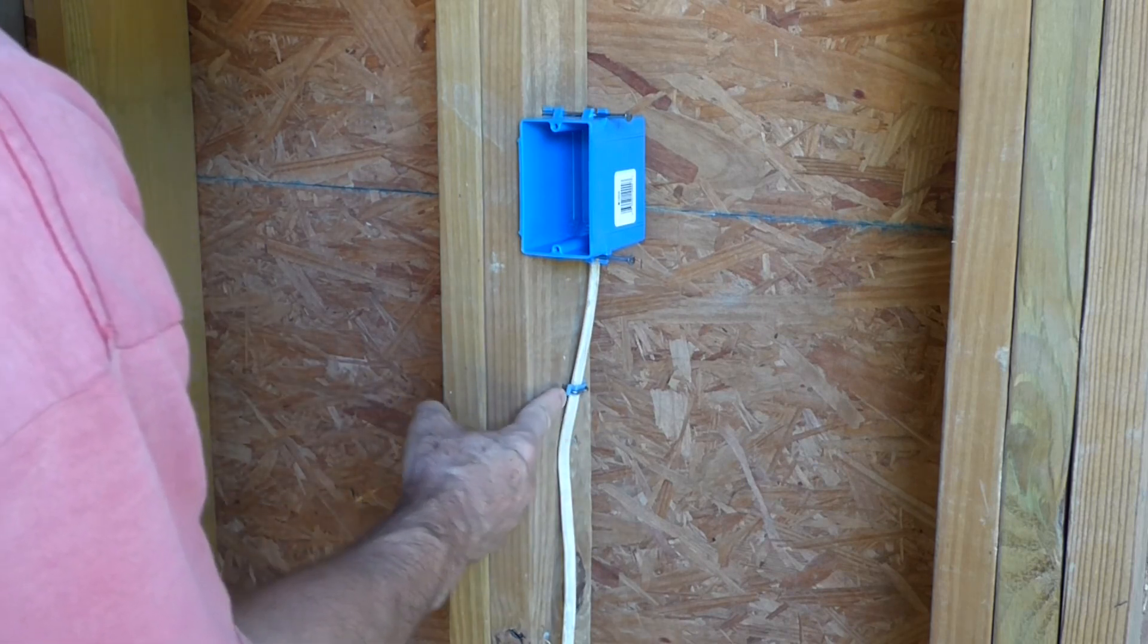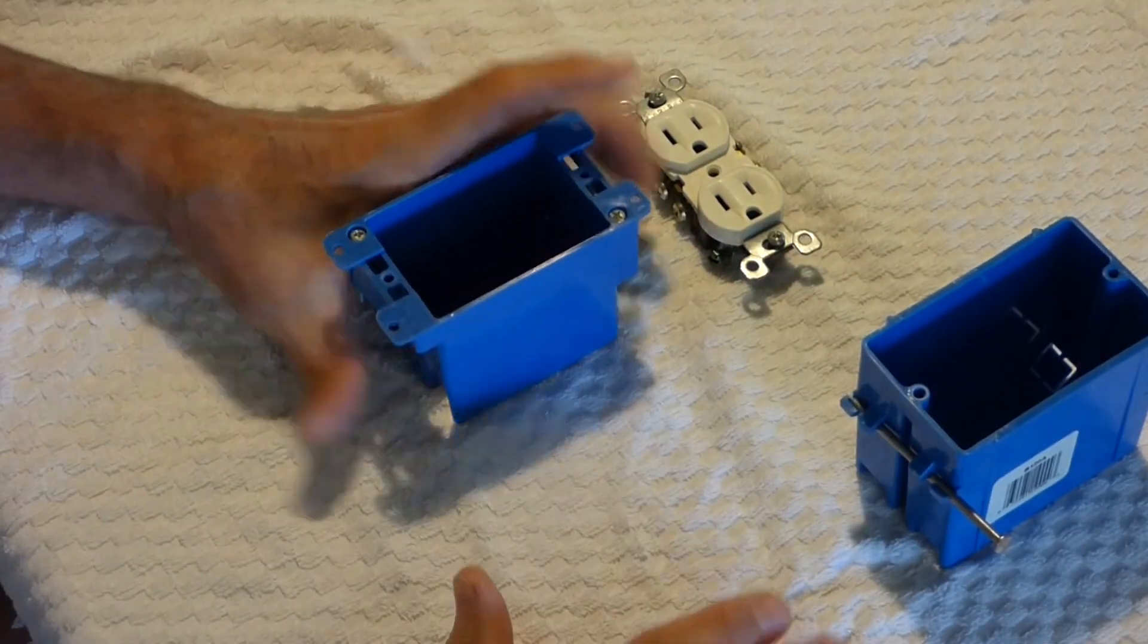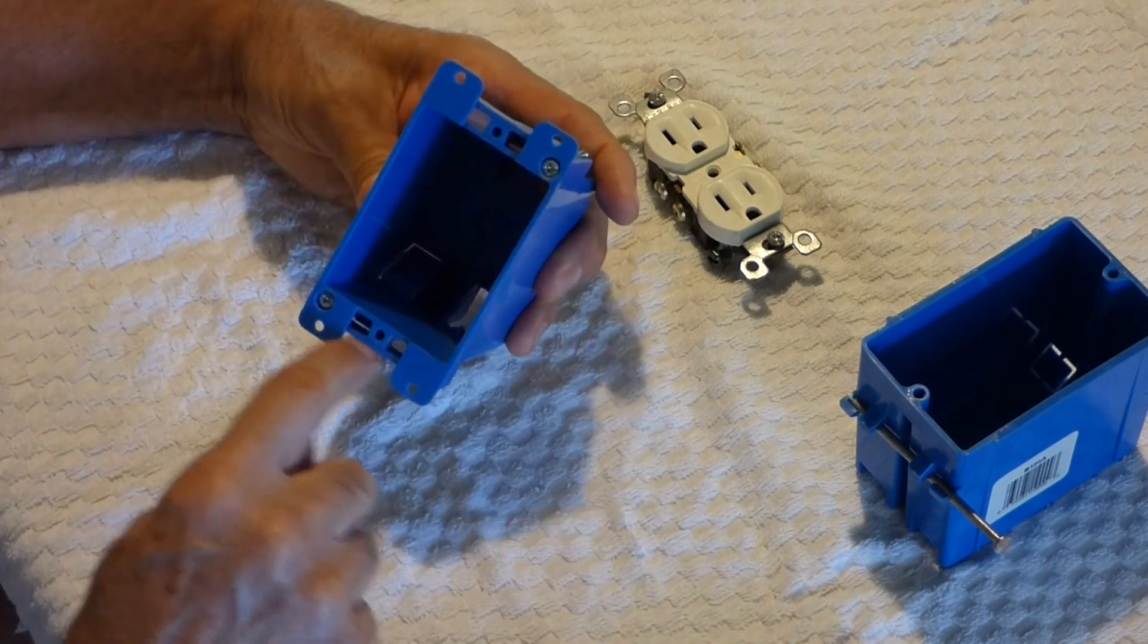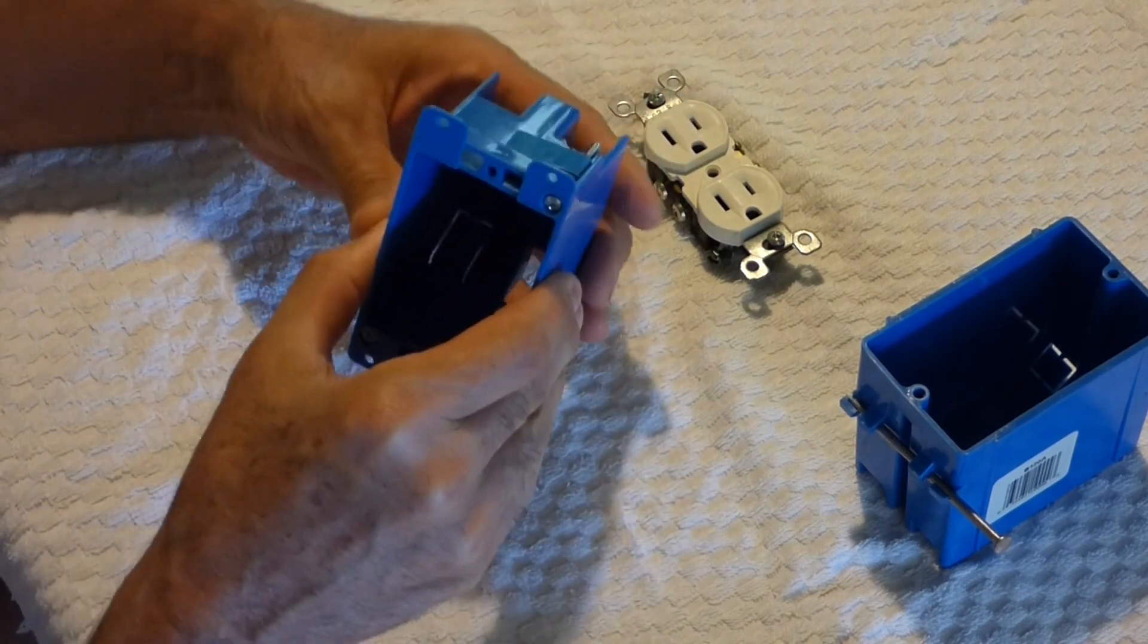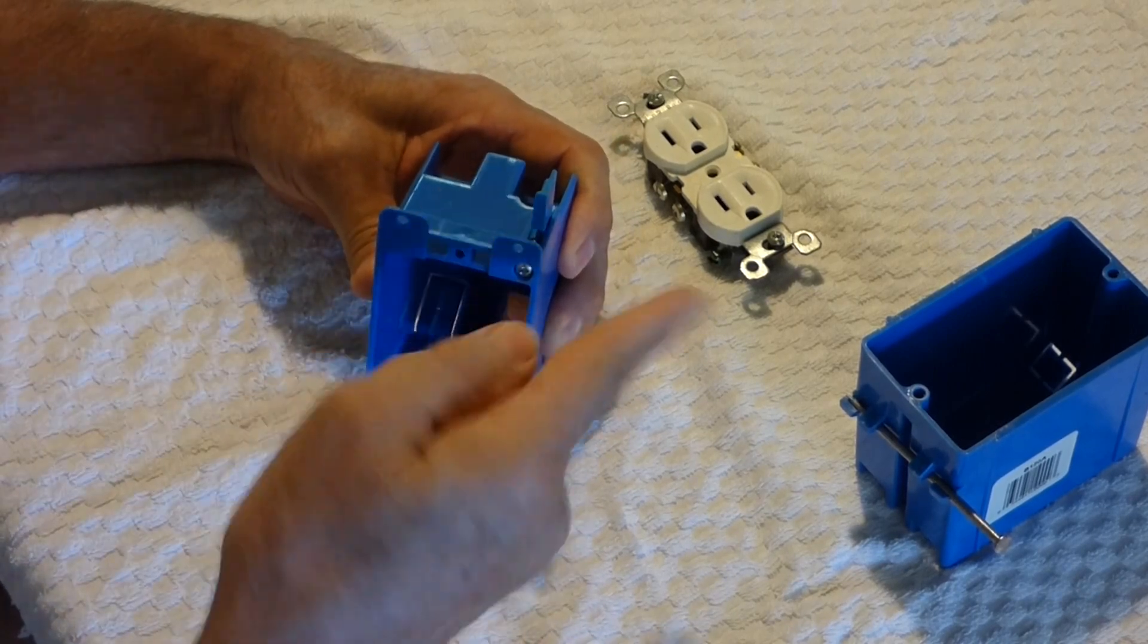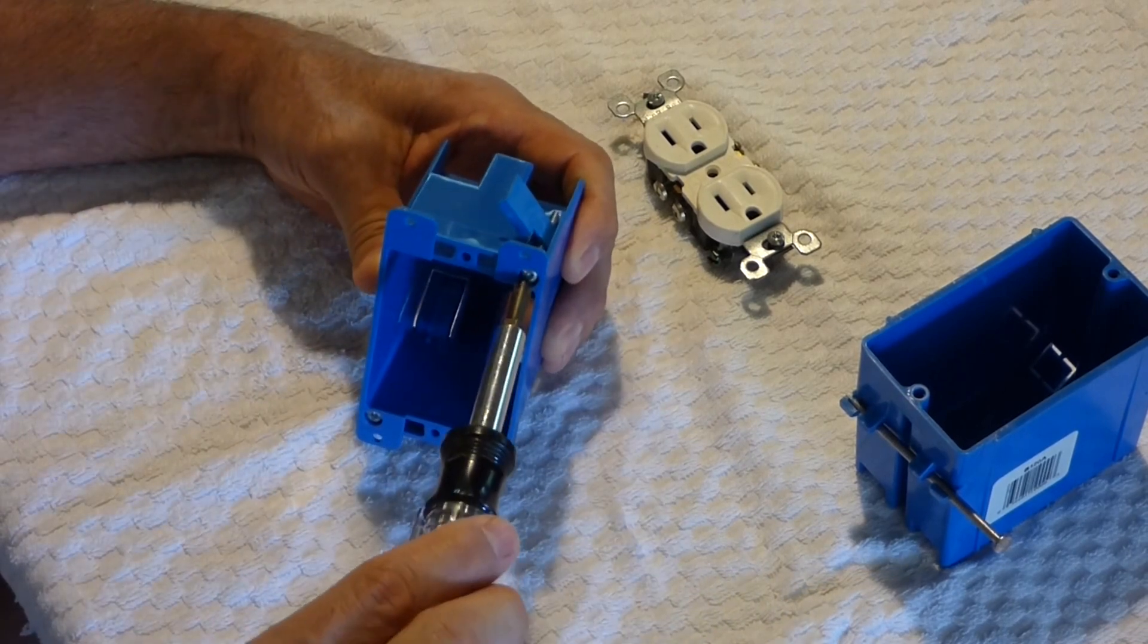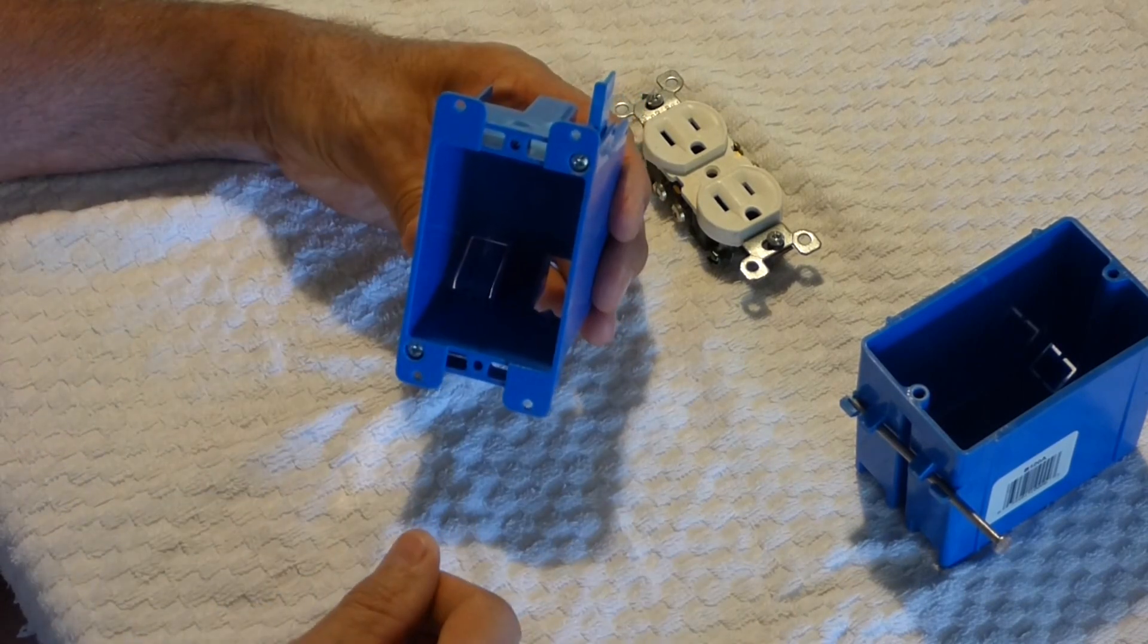You want to drive that staple down snug, but not far enough to damage the wire. If you already have a house that's sheetrocked and you want to add an outlet or switch, then you'd use a remodel box. You outline the box with a pencil, cut the sheetrock out, slide the box in the hole, and tighten these screws down. You see that tab flipped up, and the sheetrock will pinch in between the tabs and hold this box in place. You can pull the wire up through and add an outlet or a switch.